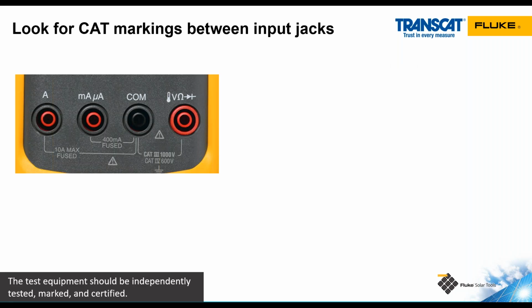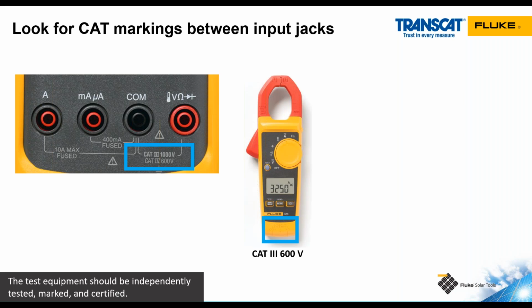Category ratings are usually very simple to find. On a Fluke tool, it's going to be printed right on the tool. This is an example of a multimeter that's category 3 1000 volt rated, category 4 600 volt rated. It is very common in almost every case. The category 3 voltage rating is going to be higher than the category 4 voltage rating because the susceptibility to transient voltage spikes is higher the closer you get to the utility.